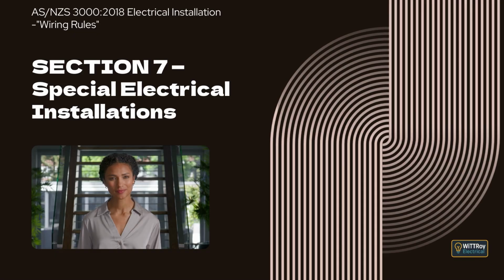Clause 7.3.4.2 Electricity generation systems incorporating batteries. This clause explains that where batteries are included in an electricity generation system, a switch capable of interrupting the battery supply must be installed adjacent to the batteries and must be clearly identified to indicate its purpose. It also explains that a single switch incorporating both alternating current and direct current switching functions may be used where permitted. Clause 7.3.5 Overcurrent protection. This clause introduces the requirements for overcurrent protection in electricity generation systems.